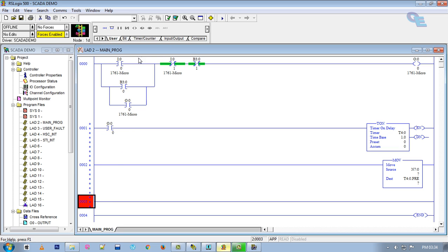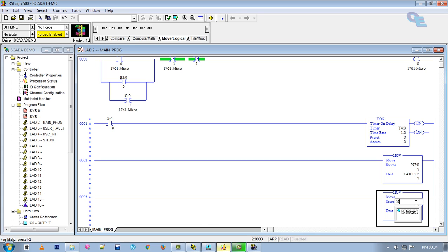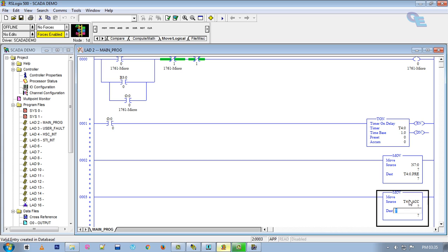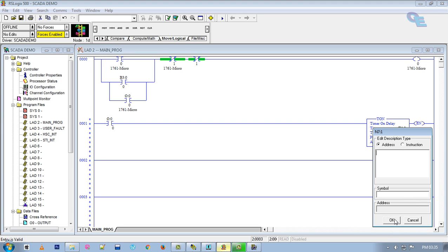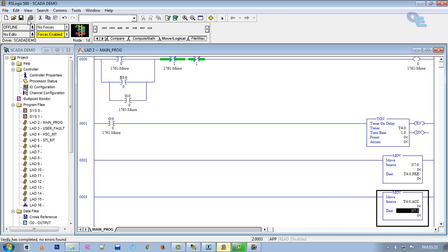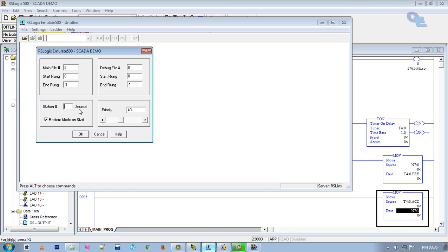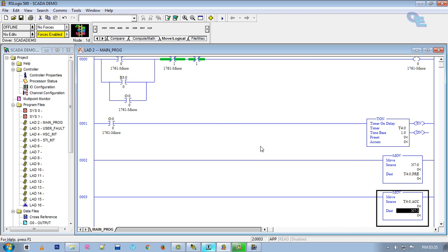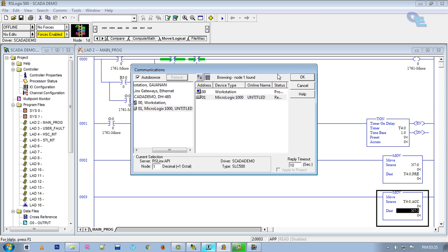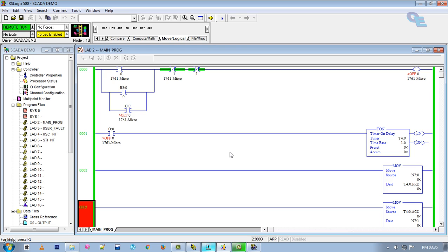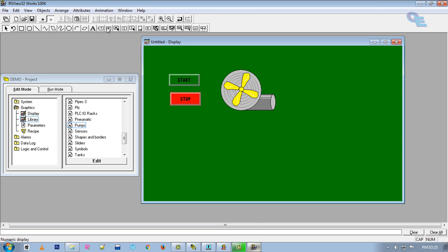Take another rung and add one MOV block. Move T4:0.ACC (accumulator value) to N7:1, so the accumulator value will be stored in N7:1 to display in SCADA. Verify file, verify project, and save. In the emulator, open the file again — place the station number the same as before and go active. Now it is in run mode.